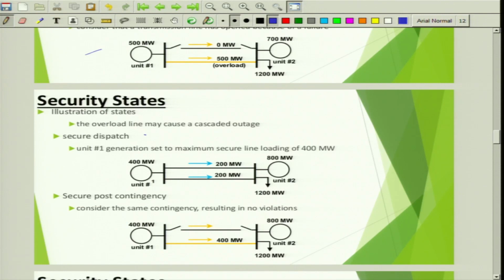Next, secure dispatch. Now what is happening? Unit 1 generation is set to a maximum secure line loading of 400 megawatt. Earlier, unit 1 was supplying 500 megawatt. Now reduce the generation of unit 1 to 400 and increase the generation of unit 2 to 800. So even if there is a possibility of line violation, still this cannot happen, the violation cannot happen. 200 each is being supplied from each line, right.